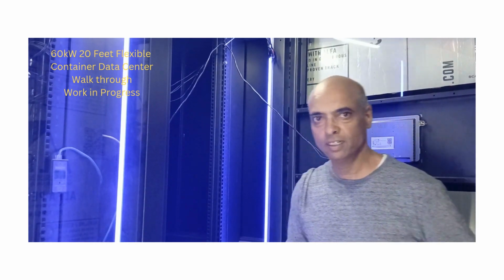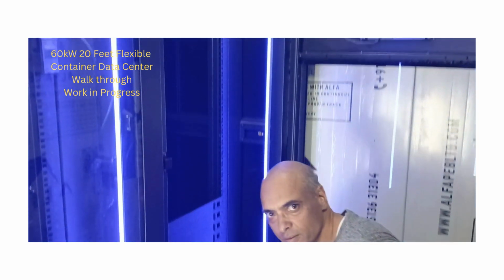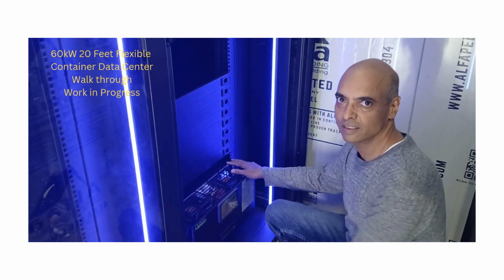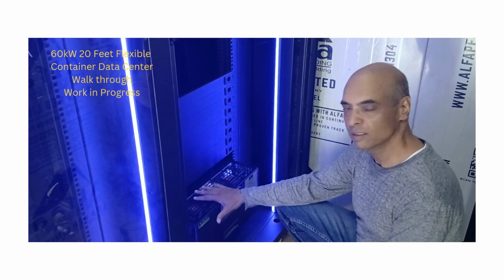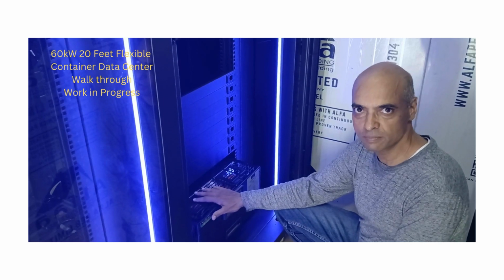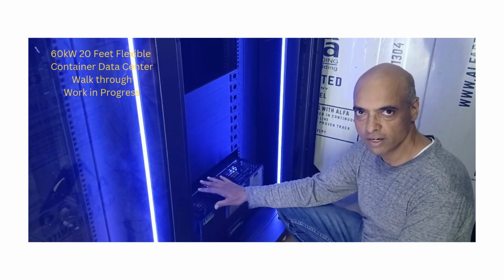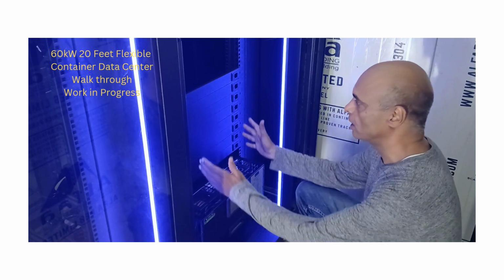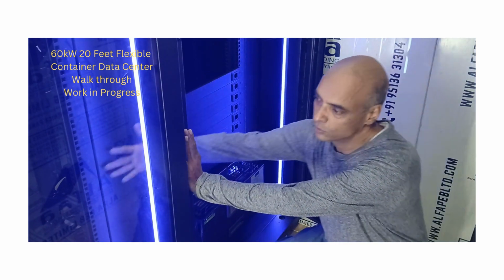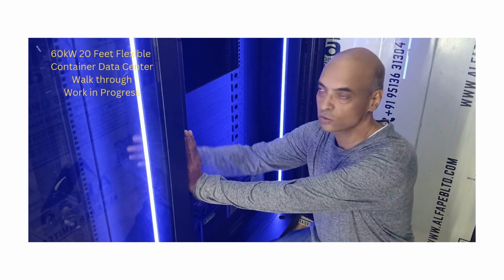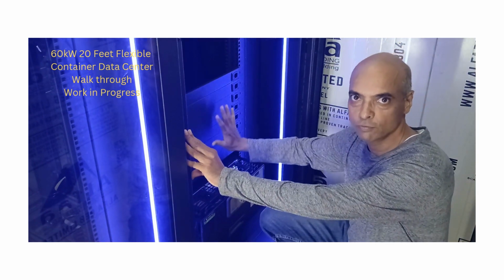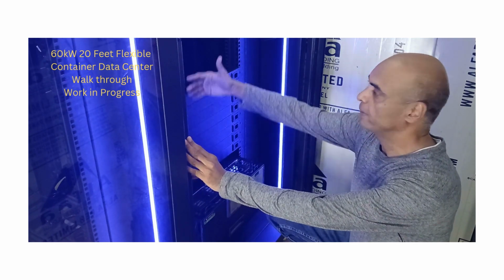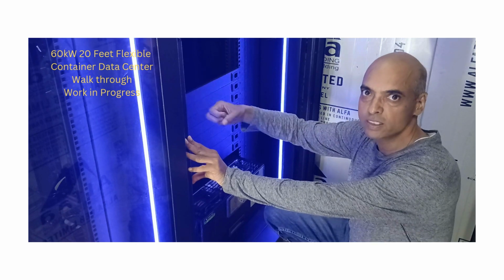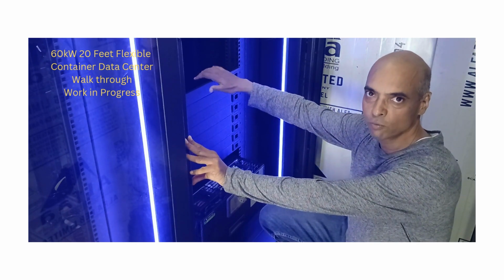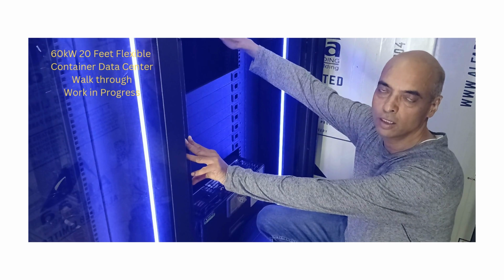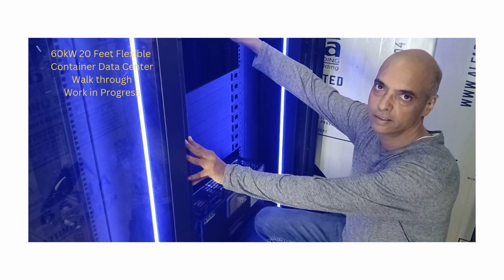I would like to show you how that works. Below me is an in-rack modular air conditioning system, which is AC fan driven. The air cooling goes up from here and passes through the right and left sides, so the cooling is always in front of the servers. These panels let the air cooling be sucked in by every server, and the hot air goes behind the IT rack.